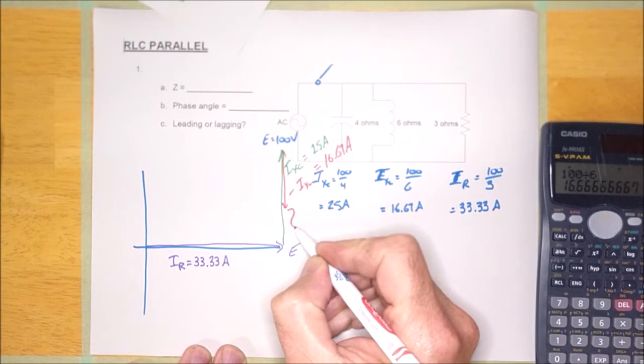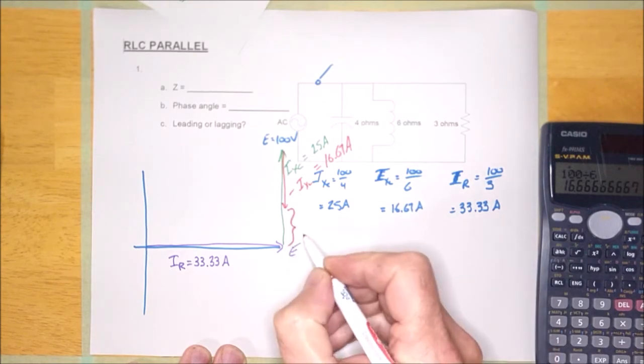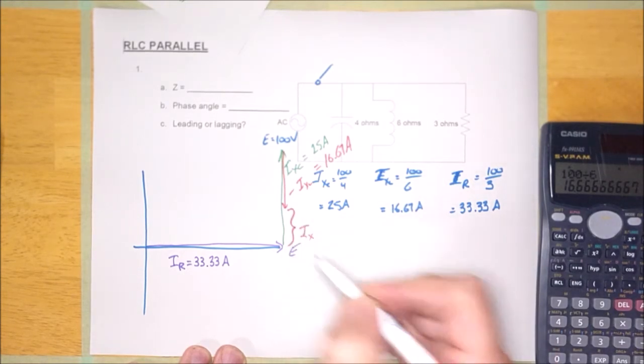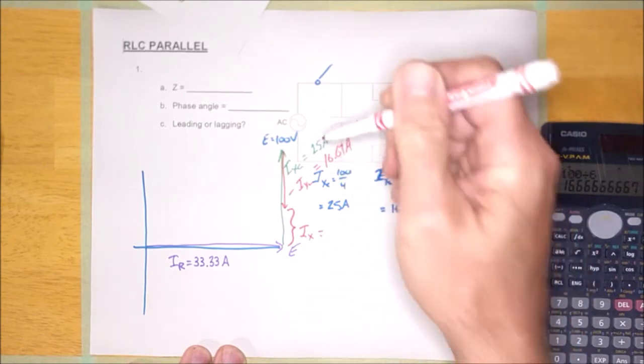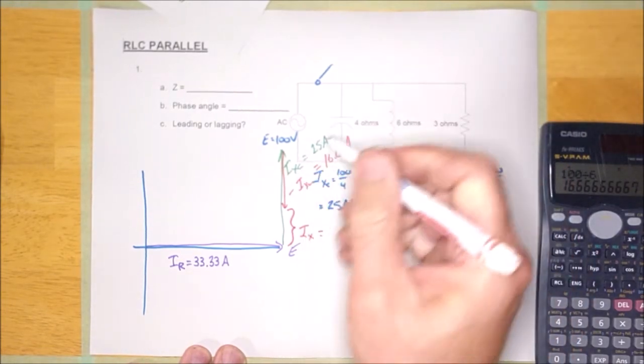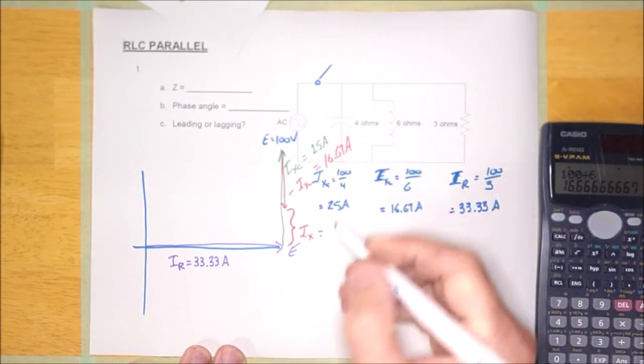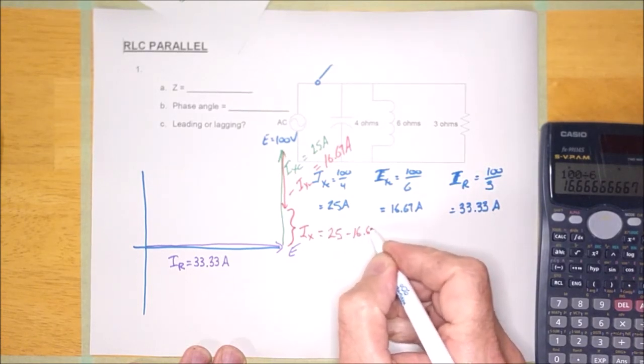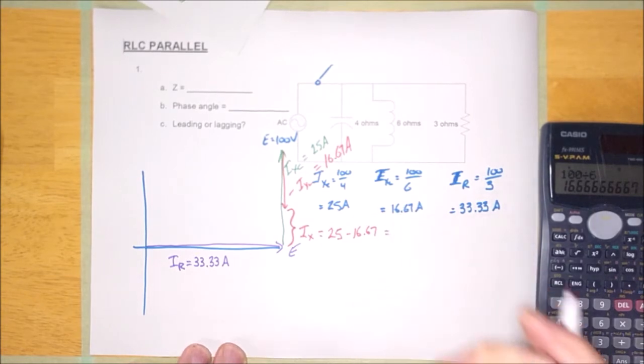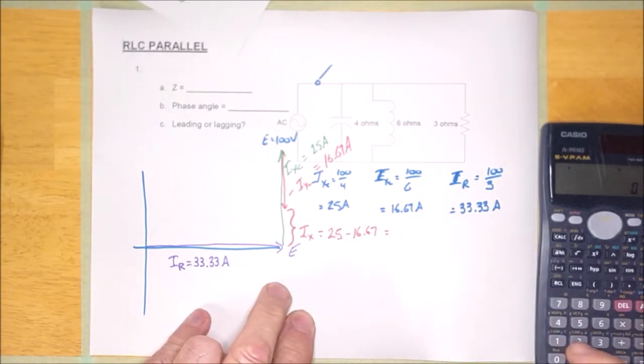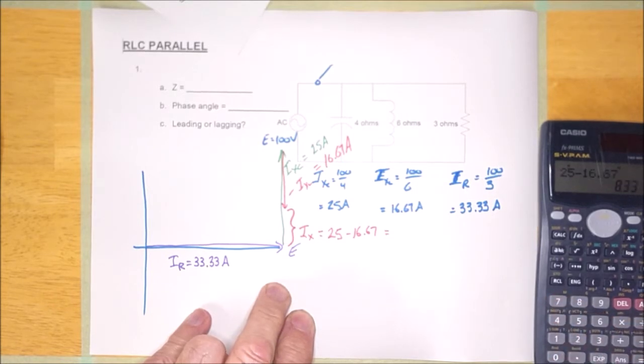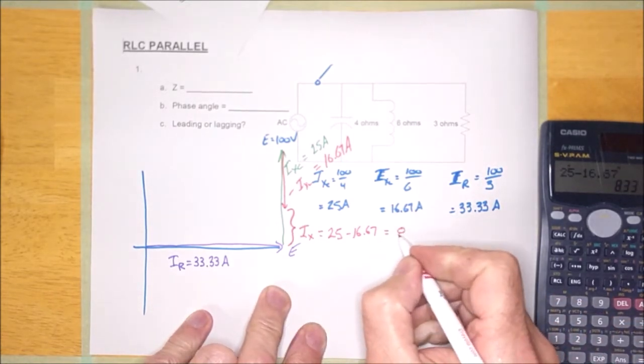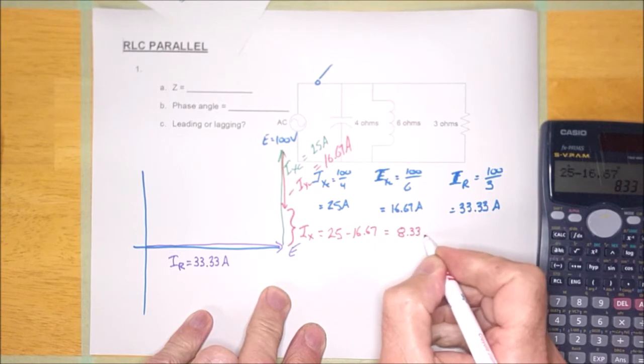And this little business right here, guys, that is going to be called IX. And IX is going to be the difference between these two. Just take the bigger one and subtract the smaller one. So it will be 25 minus 16.67. And so IX, 25 minus 16.67, it is 8.33 amps.